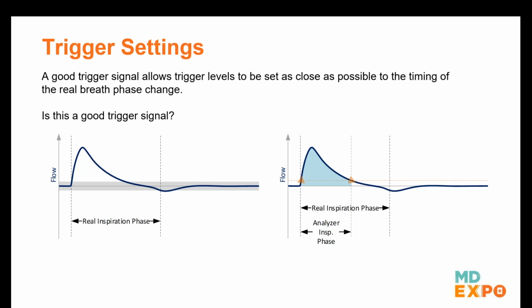However, the problem with this signal is at the end of the inspiratory phase: the signal is very flat and the changes are marginal within that gray area where we don't want to be. So it's very hard to set a trigger setting here when the inspiratory phase is over. Do you all agree on that? If we set it to the same level but on a falling edge as our stop trigger, then we could trigger, but the inspiratory phase that the analyzer detects is way shorter than the real inspiratory phase. And that's going to affect all our measurements of breath-based parameters.